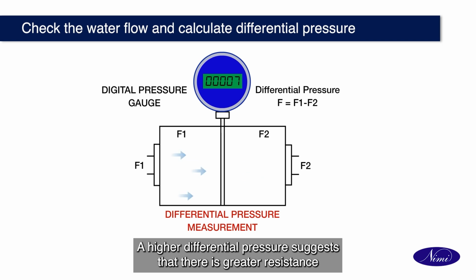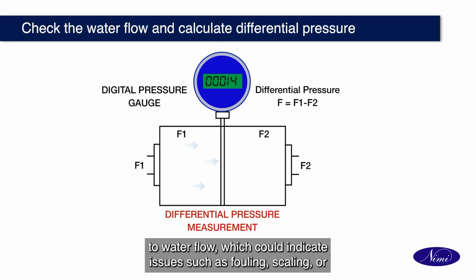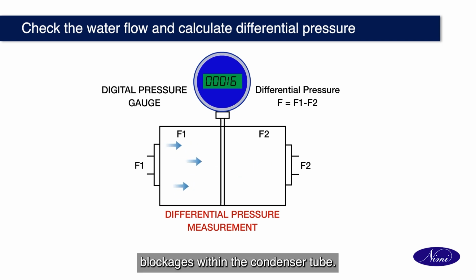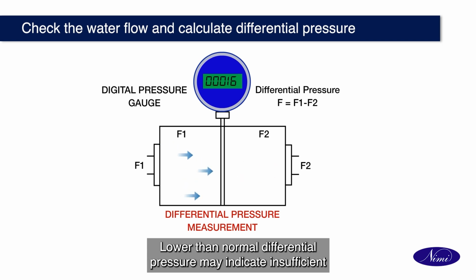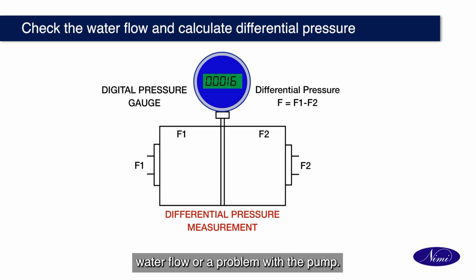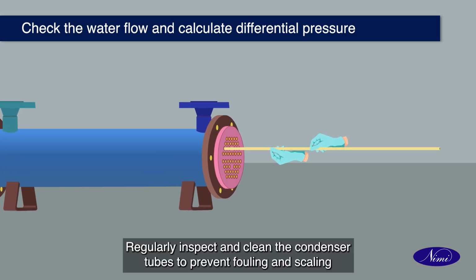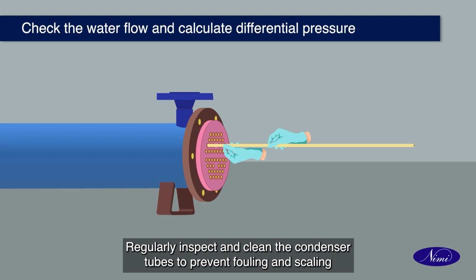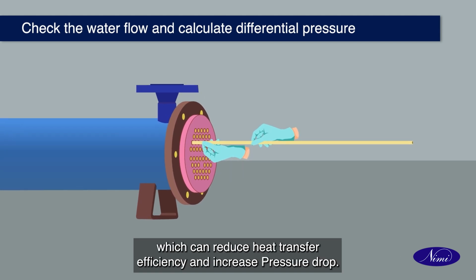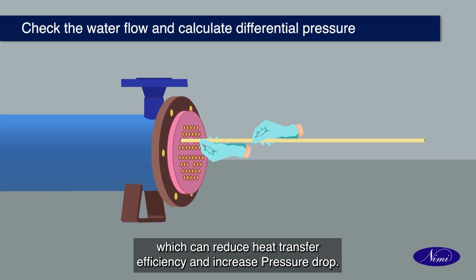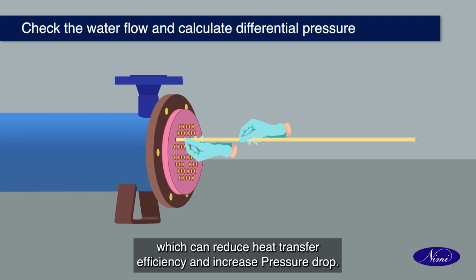Interpreting differential pressure. A higher differential pressure suggests that there is greater resistance to water flow, which could indicate issues such as fouling, scaling, or blockages within the condenser tubes. Lower than normal differential pressure may indicate insufficient water flow or a problem with the pump. Cleaning and maintenance. Regularly inspect and clean the condenser tubes to prevent fouling and scaling, which can reduce heat transfer efficiency and increase pressure drop.